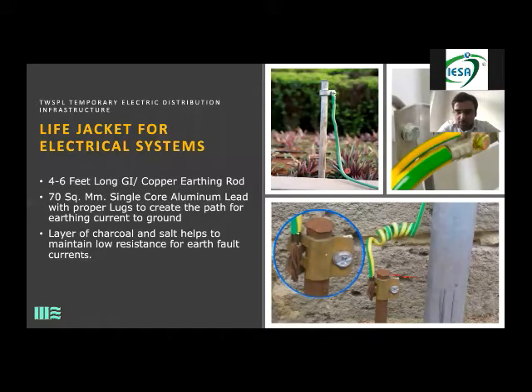Neutral earth for the genset. If you're using house power, then the neutral is already earthed from the grid, so you don't need to worry about that. The only thing you need to worry about is body earth of your hangers, your trussing, everything from scaffolding, anything which has a light on top of it. It could be your single pagoda also, which has one bulb on it. If a live wire touches the metal, it becomes electrically charged. So earthing is a very, very important thing for any electrical distribution.